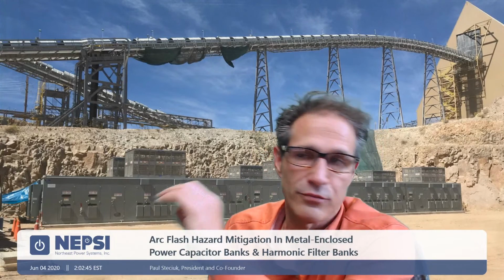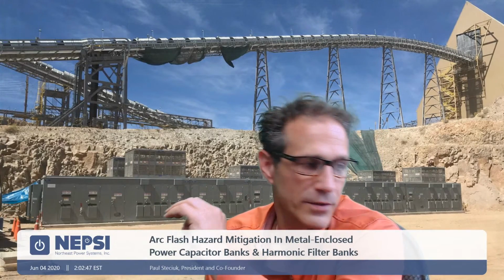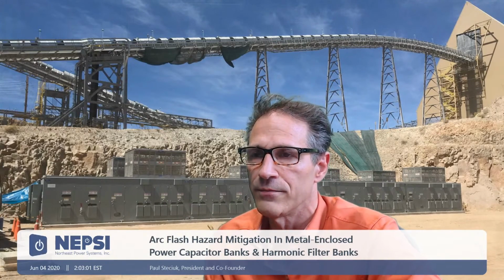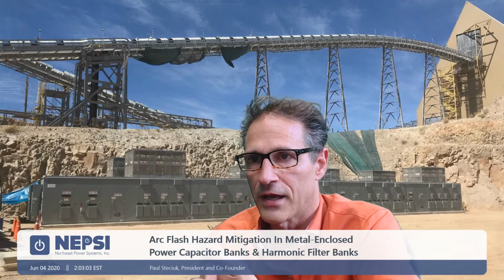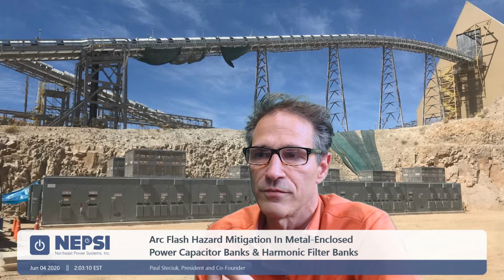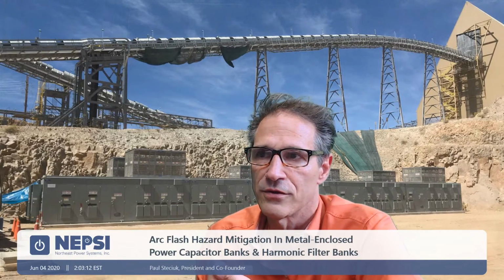The mines use what's called a zero harm concept, where health, safety, and environment are considered, and this is a critical matter that should always be considered when designing harmonic filters. When you think about arc flash hazard mitigation, two things come to mind from our standpoint. One is the actual hazard to people standing in front, the operating personnel. The cost of their life, the cost of them being injured, and the litigation cost that follows.